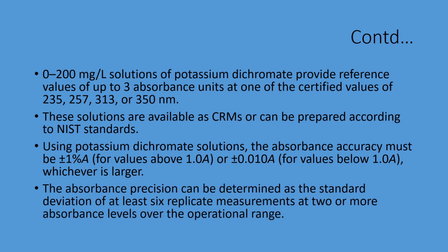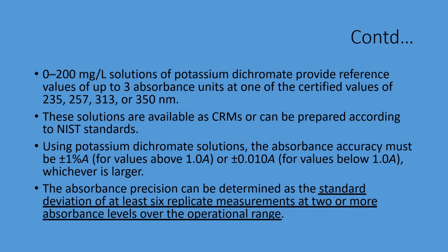The absorbance precision can be determined as the standard deviation of at least 6 replicate measurements at 2 or more absorbance levels over the operational range.